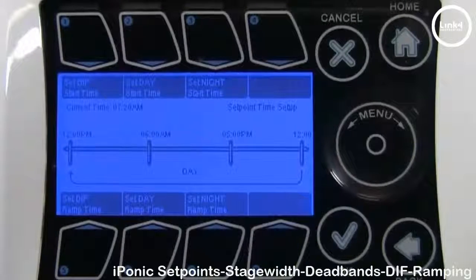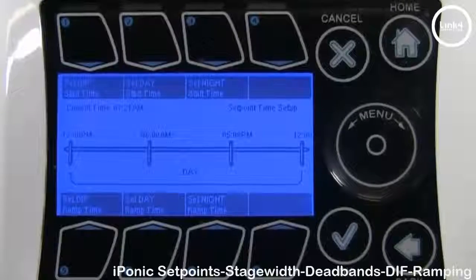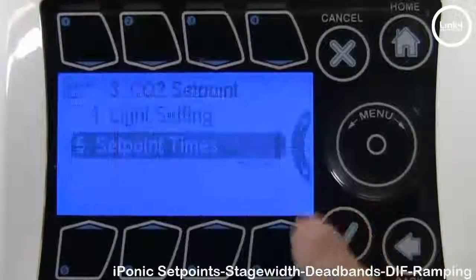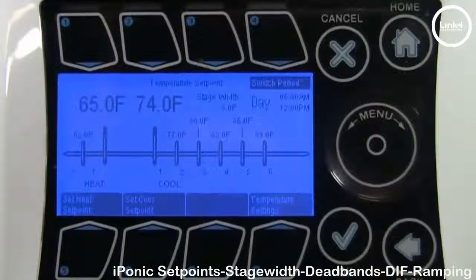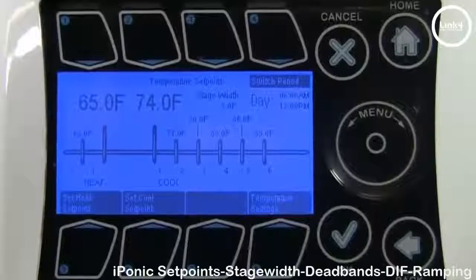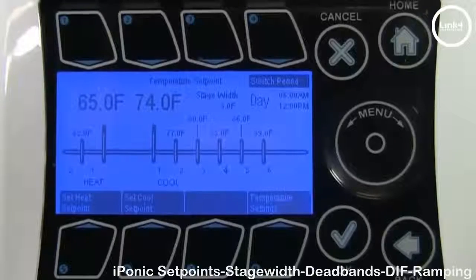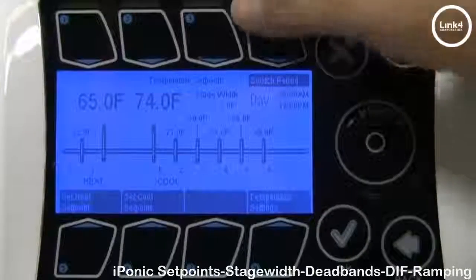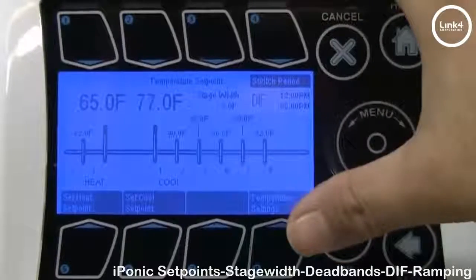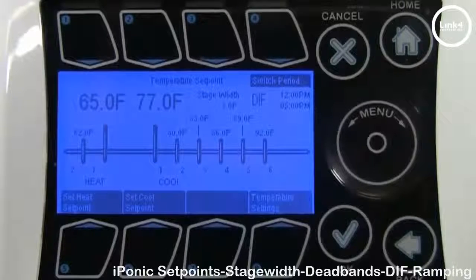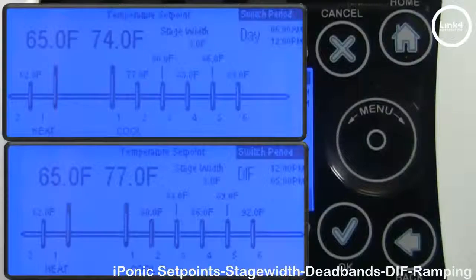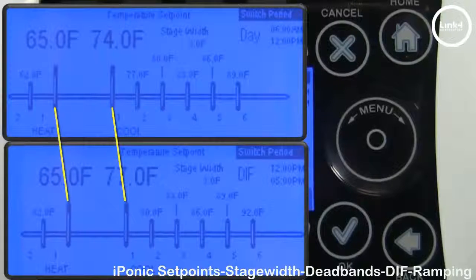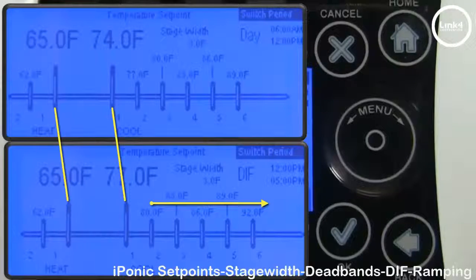Now we have 30-minute ramps on all our set points. Let's go back, save our changes, and go back to temp set points. In temp set points, our daytime period is 65 to 74, undergoing temp changes from the nighttime set point values. Going to DIF 65 to 77, starting at 12 p.m. to 5 p.m., with this range slowly transitioning due to our ramp, gradually increasing targeted temperature values — for example, with the cool set point increasing, you also see your temp stage values increase as well. Our nighttime period starts from 5 p.m. to 6 a.m., transitioning to cooler temp ranges both in cool and heat set points and staging set point values.